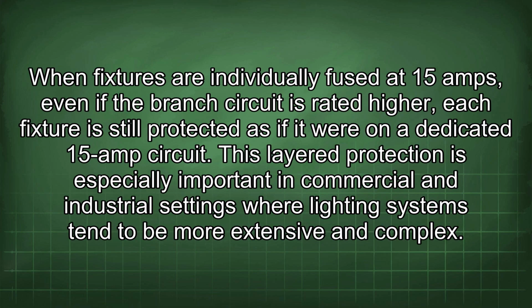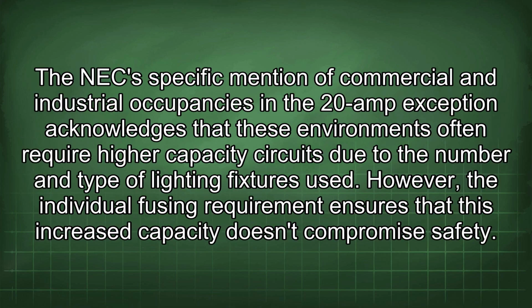When fixtures are individually fused at 15 amps, even if the branch circuit is rated higher, each fixture is still protected as if it were on a dedicated 15 amp circuit. This layer of protection is especially important in commercial and industrial settings where lighting systems tend to be more extensive and complex. The NEC's specific mention of commercial and industrial occupancies in the 20 amp exception acknowledges that these environments often require higher capacity circuits due to the number and type of lighting fixtures used. However, the individual fusing requirement ensures that this increased capacity doesn't compromise safety.